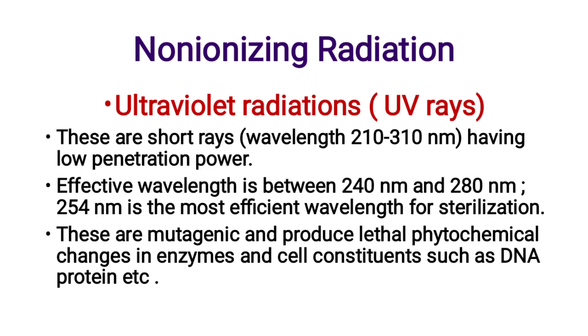Non-ionizing radiation includes ultraviolet radiation — that is, UV rays. These are short rays with a wavelength of approximately 210 to 310 nanometers, having low penetration power. The effective wavelength is between 240 nanometers and 280 nanometers, and among these, 254 nanometers is the most efficient wavelength for sterilization.